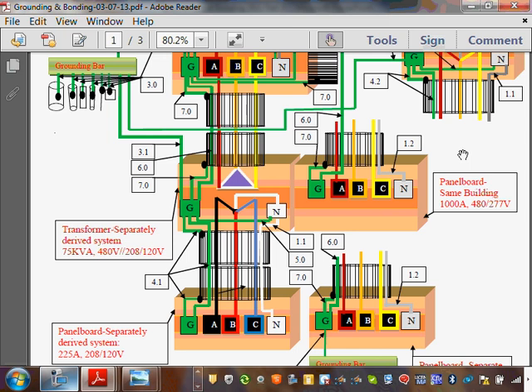So you loop it, bond the conduit, and get into the ground bar inside the transformer. So let's go, guys, size 6.0. I'm bringing on the primary side, you bring 3 wires, because it's delta, and an equipment grounding conductor if it's an EMT conduit, if it's a PVC conduit.